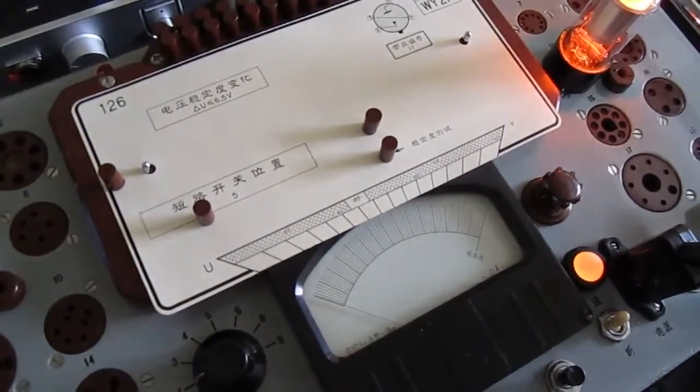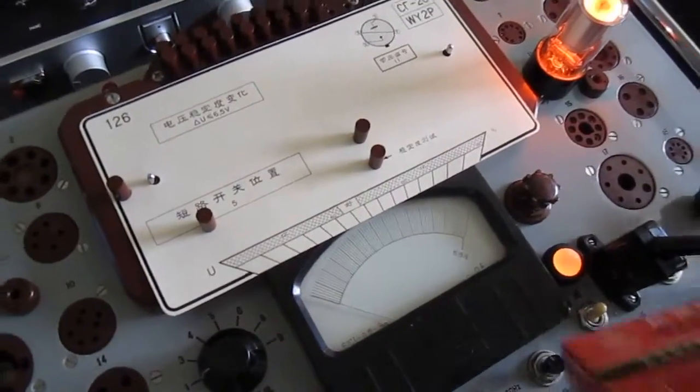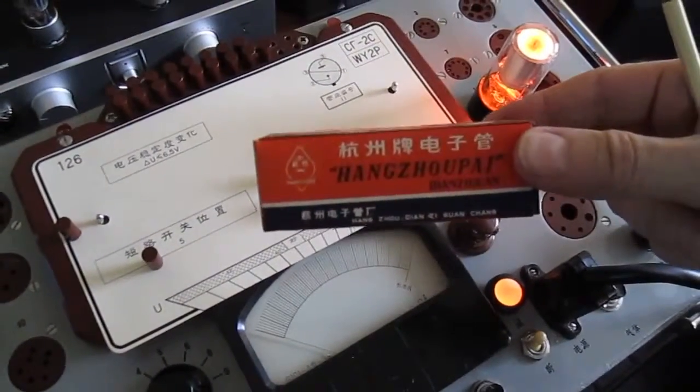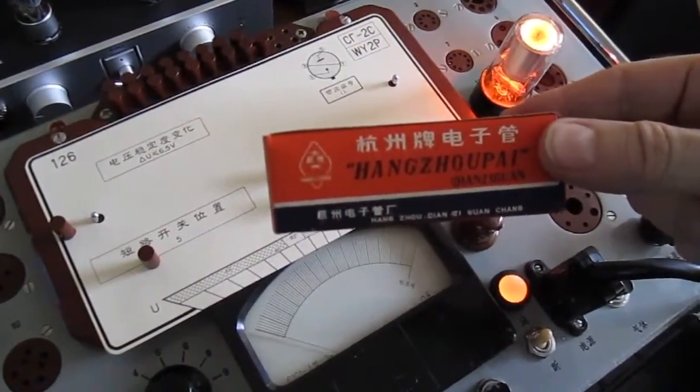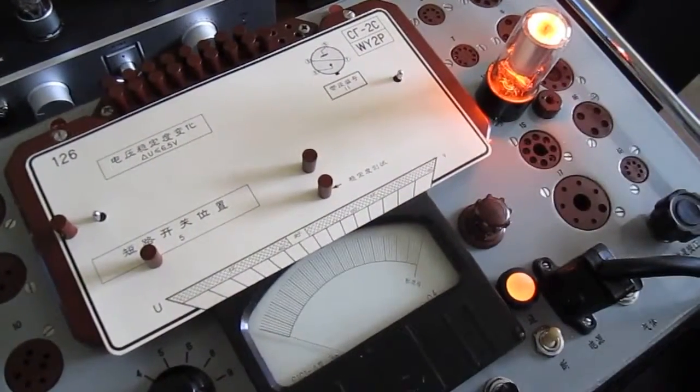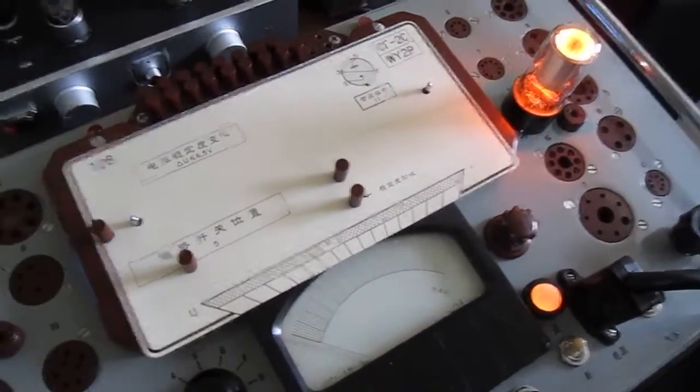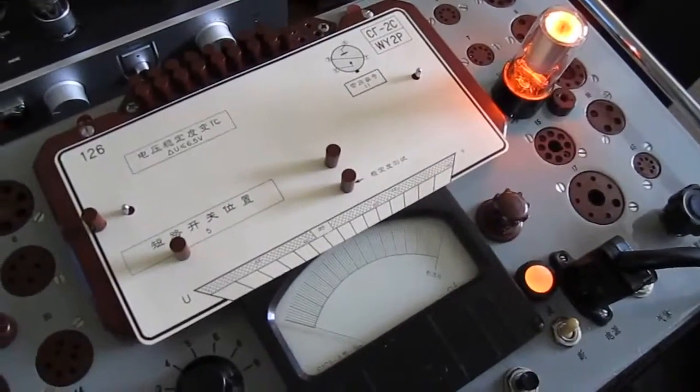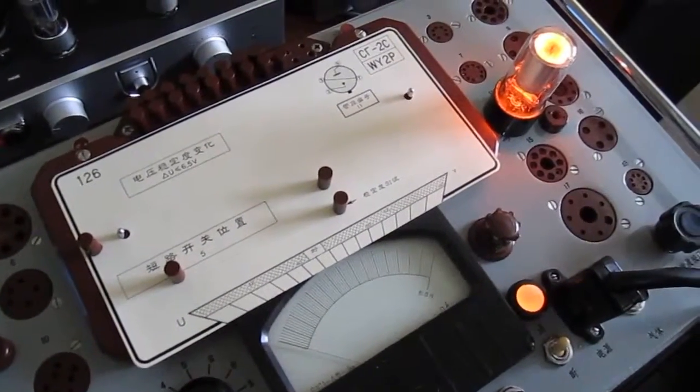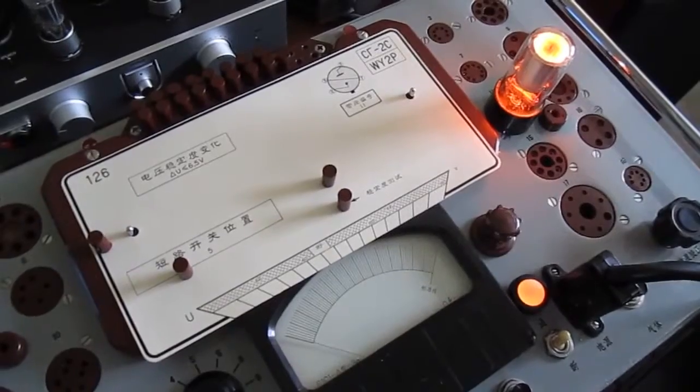Now ideally we'd be 75 volts. This particular brand, which is the Hangzhou tube here in China, is pretty darn good. If I get a box of 50, you'll see a variation anywhere from maybe 74 to maybe 75.5. Not bad at all, at least for the newer tubes.